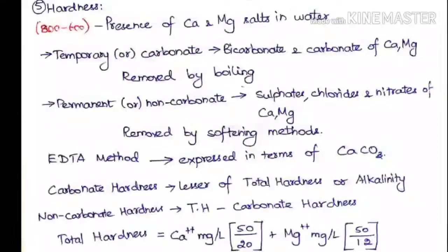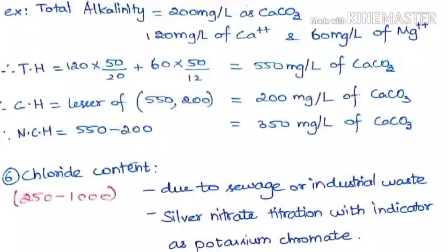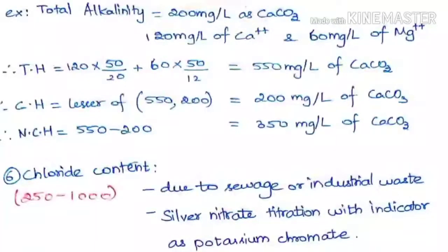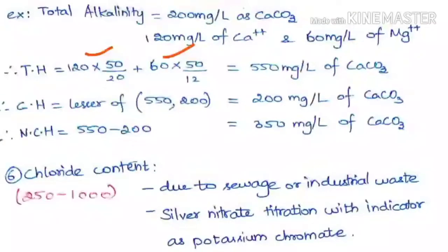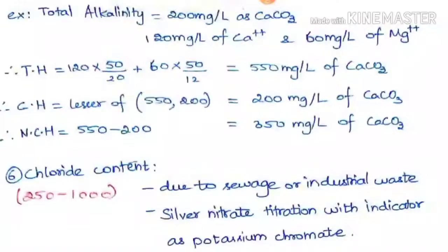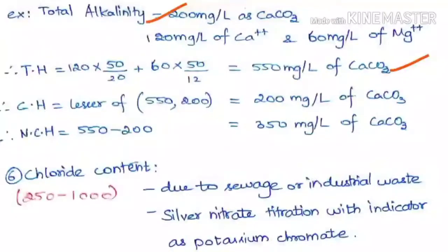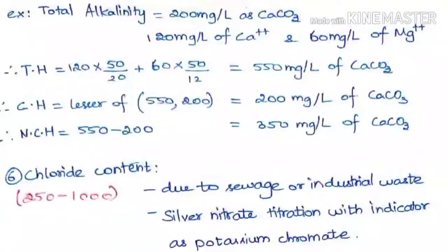Example: Total alkalinity = 200 mg/L as CaCO3, calcium concentration = 120 mg/L, magnesium concentration = 60 mg/L. Total hardness = (120 × 50/20) + (60 × 50/12) = 550 mg/L as CaCO3. For carbonate hardness, take the lesser of total hardness (550) and total alkalinity (200), which gives carbonate hardness = 200 mg/L. Non-carbonate hardness = 550 − 200 = 350 mg/L as CaCO3.